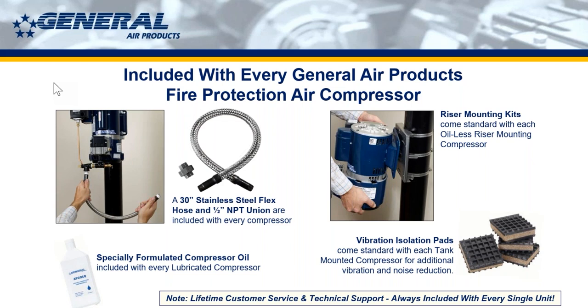Another thing I'd like to bring up is the oil. If you have an oil lubricated compressor, you may see when you get it to a job site that in the sight glass there's a little oil in there. There is not enough oil to run it on. We're not allowed to ship lubricated units with oil in them. We're just not allowed. The reason there's oil in there is because we run test everything that leaves our building and see it working before it goes into a box. So there's just enough oil in there for us to safely run the unit. You still need to add the oil that comes with the unit.